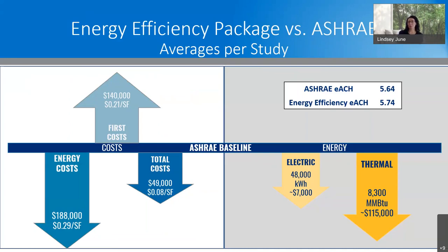So as far as the airborne transmission risk reduction is concerned, on average, the EACH of the energy efficiency package was pretty much in line with the ASHRAE package, meaning that the energy efficiency package savings can be achieved without compromising IAQ. While this is promising news in respect to the energy efficiency package versus the ASHRAE package based on that early ASHRAE guidance, we do need to consider how the energy efficiency package compares to the pre-COVID building operation. Next slide.